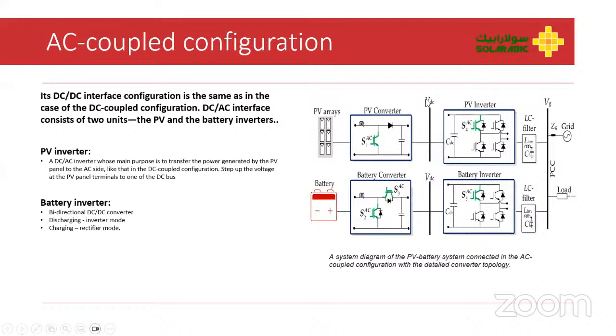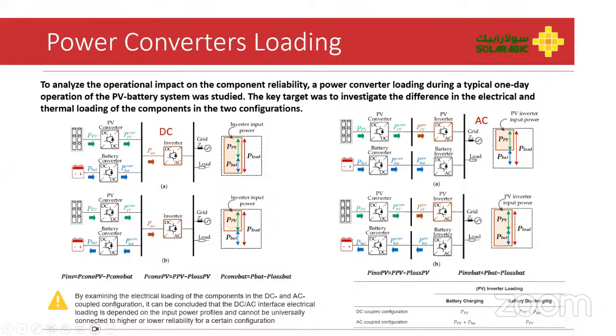In an AC coupled configuration, the DC-DC interface is the same, but on the DC to AC interface, you have the inverter and the battery inverter. The PV inverter is doing the same job as in the DC coupled configuration, and we have a battery inverter, which is a bidirectional converter, working in an inverter mode for discharging and working as a rectifier for charging. In order to analyze the operational impact on the component reliability, the power converter loading during a typical one day of operation is studied. The key target is to investigate the difference in the electrical and the thermal loading of the components in the two configurations. On the left, we have the DC coupled configuration. On the right, we have the AC coupled configuration. We see here in A that during discharging, the inverter is facing a loading stress from the PV converter and the battery converter.